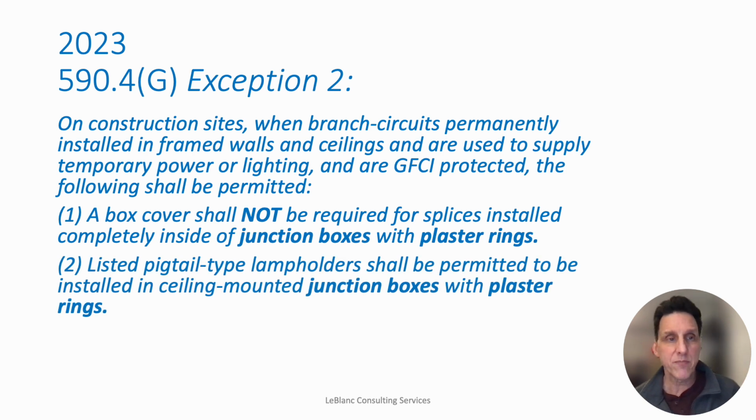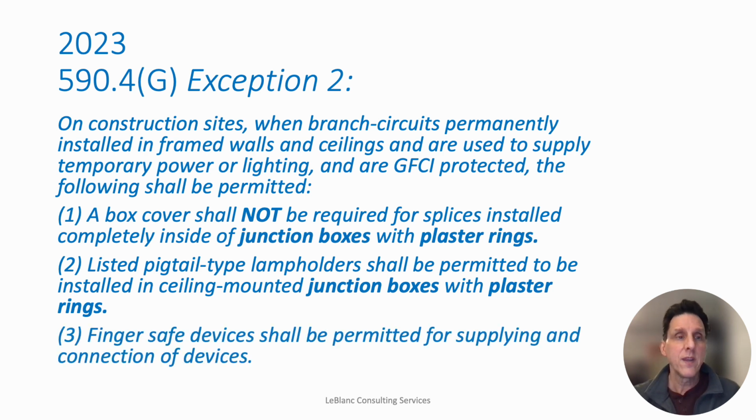And if you want to install some temporary lighting, item 2 says listed pigtail lamp holders are permitted to be installed in ceiling mounted, again, junction boxes with plaster rings is the wording. So there has to be a plaster ring in order for you to energize it for temporary lighting purposes. And then finger safe devices are also permitted for supplying and connection of devices. And I will show you some finger safe devices.